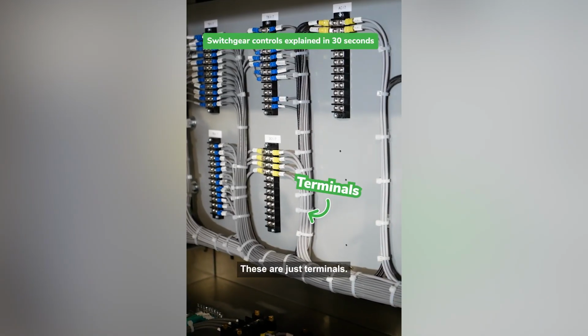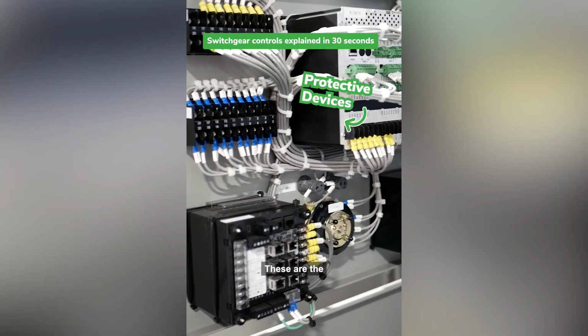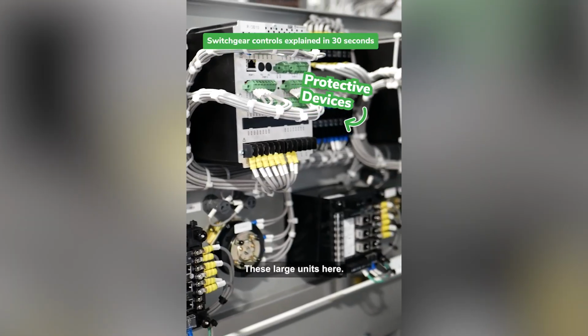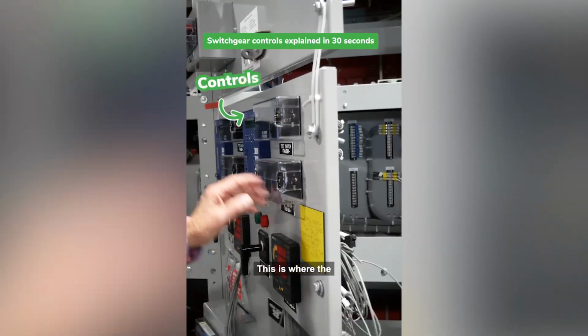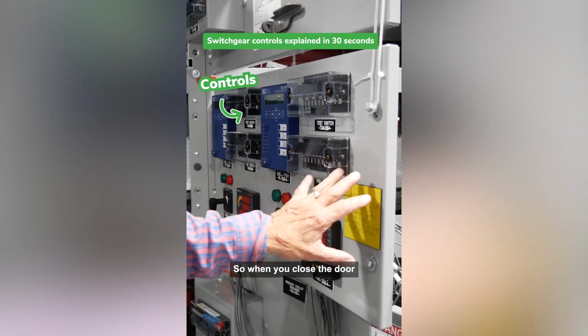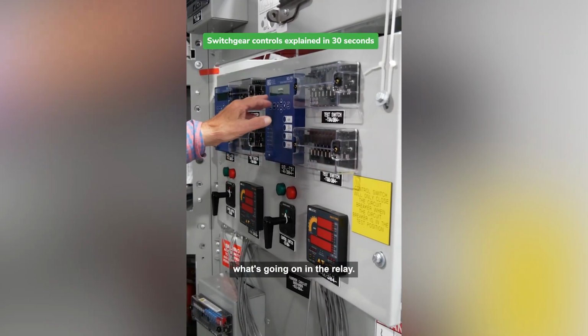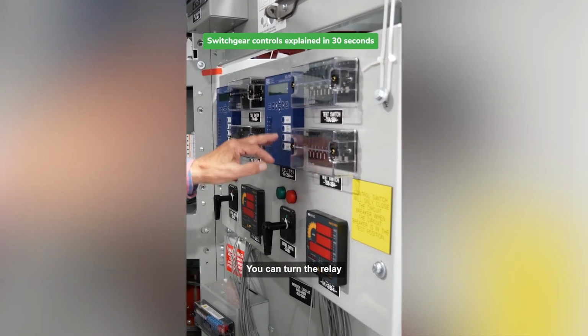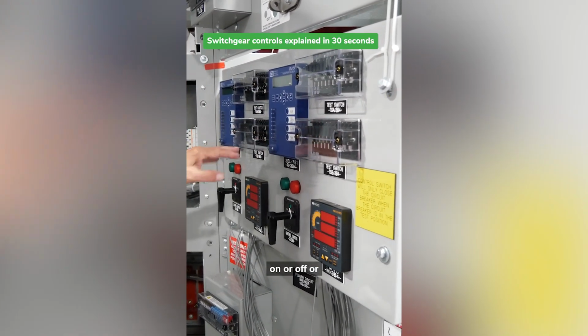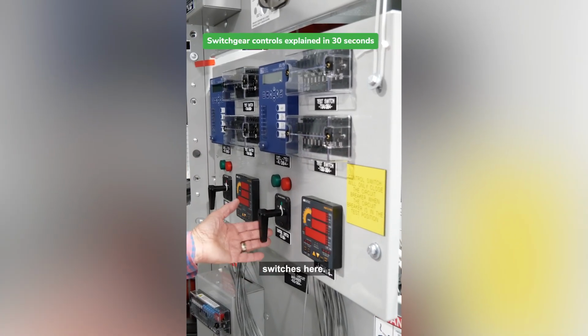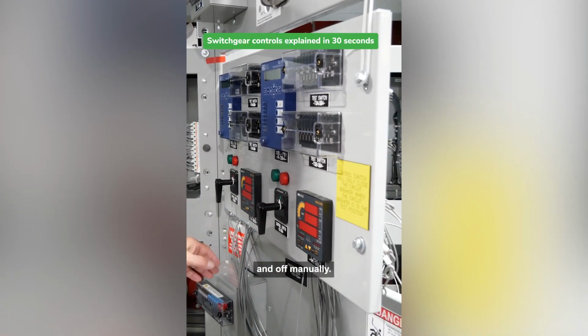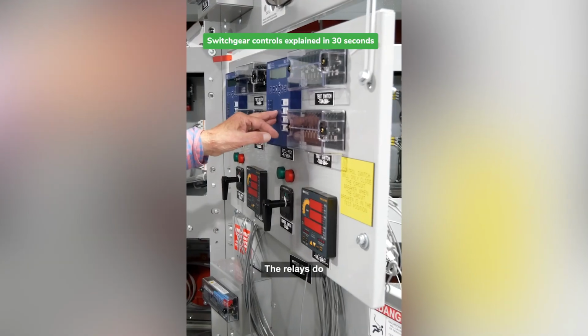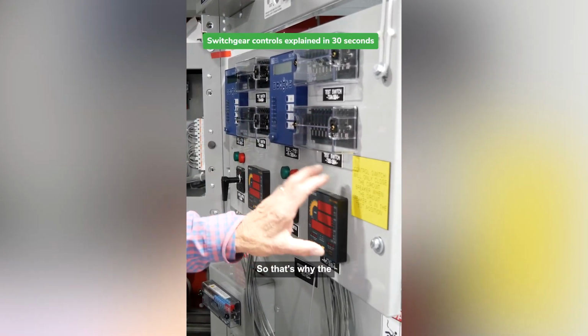These are just terminals. These are the protective devices here. These large units here, this is where the controls are. So when you close the door, here's where you can see what's going on in the relay. You can turn the relay on or off, or you've got breaker control switches here. You can turn the breakers on and off manually. The relays do it electronically. So that's why the relays are mounted here and not inside the door.